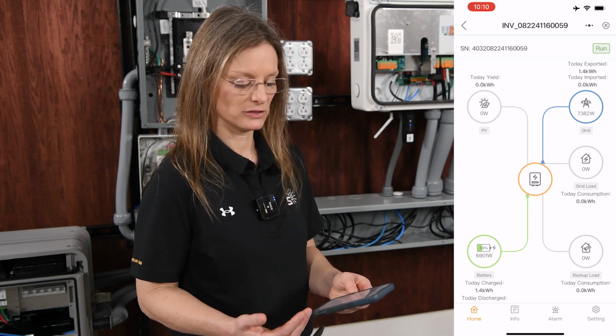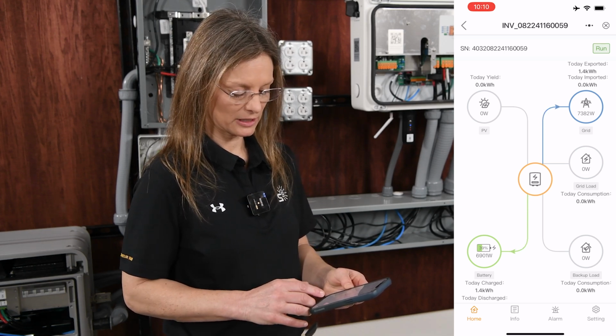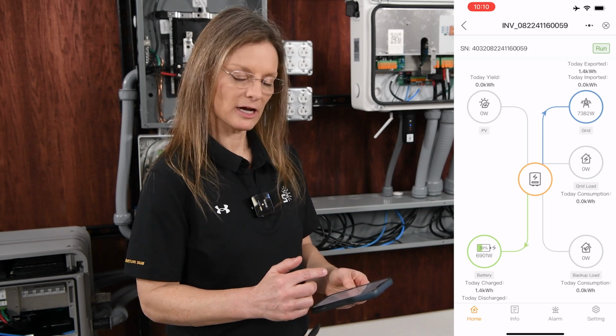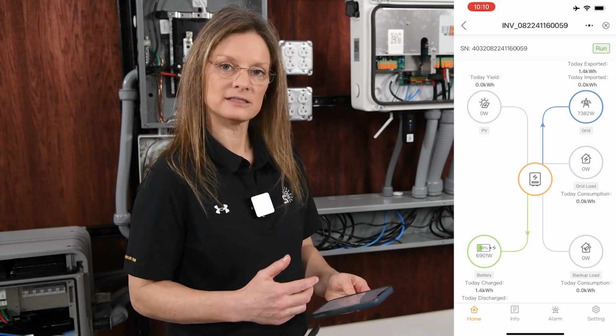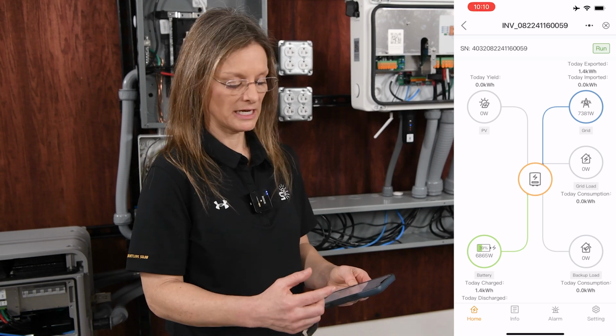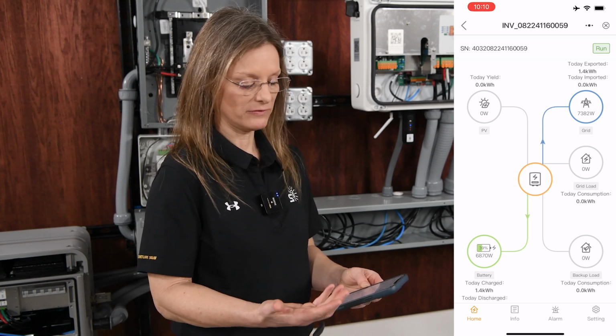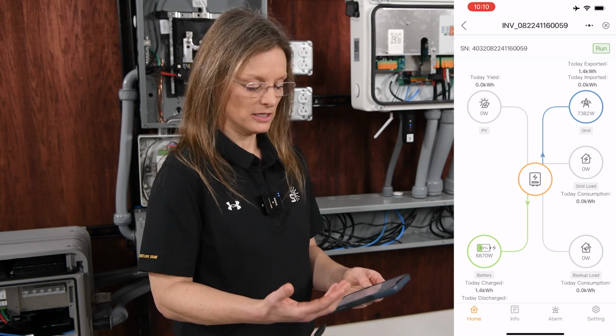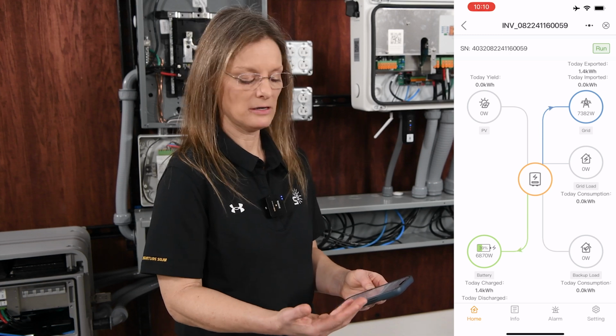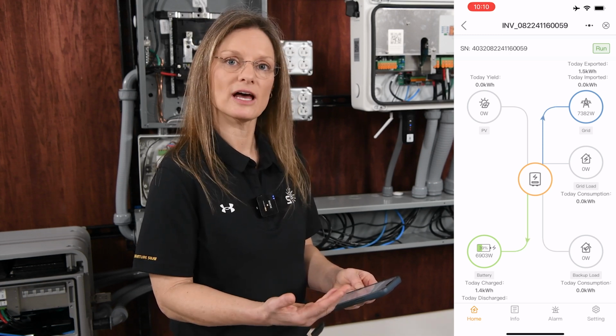We don't want to sell back to the grid, but our animated graphic shows that our batteries are charging, but somehow we're sending power back to the grid. This doesn't make sense. There is a troubleshooting process here. This tells me that possibly our CTs have been installed backwards. Now, we did install them according to the manual. In the meter, it says to install them with the arrow pointing towards the grid, which is what we did. However, the manual may have been incorrect. So there is a way that rather than going back to the meter and reversing them there, we can change them electronically. So I'm going to show you how to do that now.